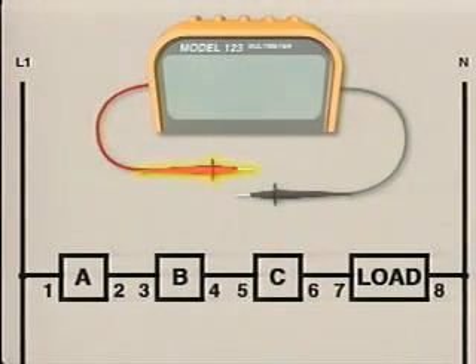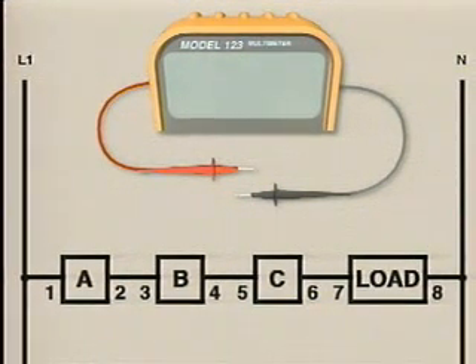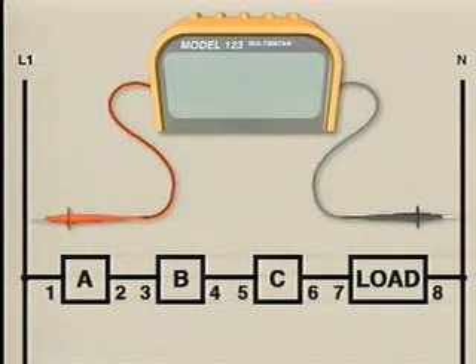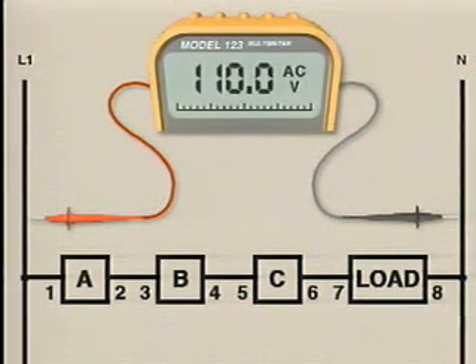In this unit, we'll show the voltmeter's red probe connected to the test point that is being checked. The black probe will be connected to what is called a reference point. A reference point is simply another point in the circuit to which the test point being checked is compared. As an example, let's use the voltmeter to see if voltage is being applied to the circuit. To make sure this circuit has the proper operating voltage, the voltmeter's test probe should be connected to L1 and neutral. With the voltmeter's test probes connected, the voltmeter's display indicates full line voltage. This means that voltage is being applied to the circuit.